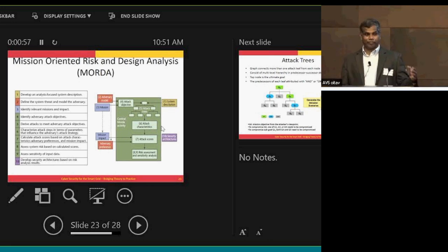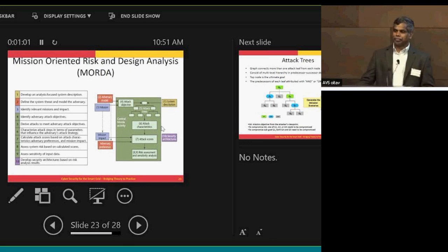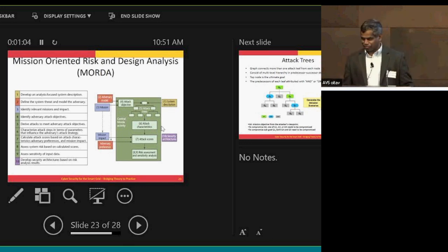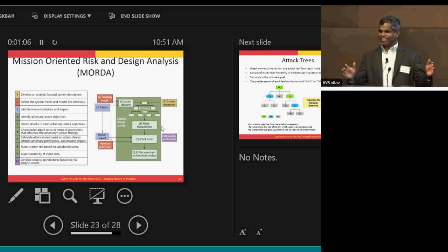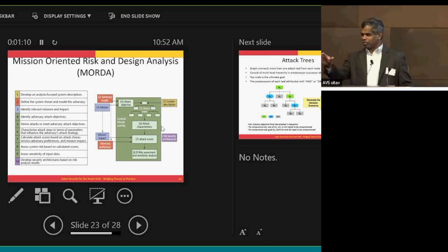A lot of industries, I'm not sure whether MISO has it, Southern California Edison, for example, have their own test bed. They have a miniaturized version of all those automation software, substation, control center, racks of RTDS simulators. They're all coupled together as a hardware-in-the-loop environment, within which they inject different attacks, poke different aspects of the system, and see the consequences.